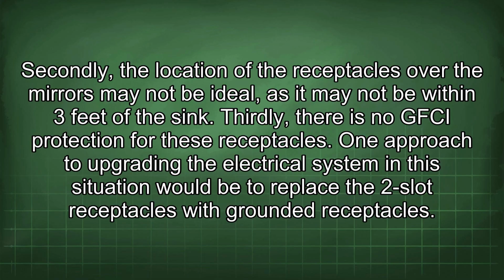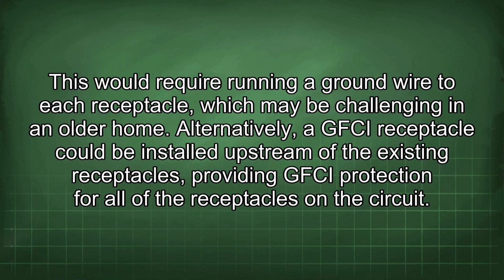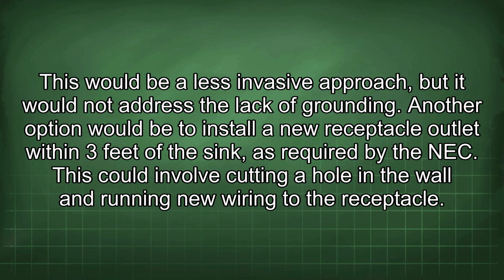One approach to upgrading the electrical system in this situation would be to replace the 2 slot receptacles with grounded receptacles. This would require running a ground wire to each receptacle, which may be challenging in an older home. Alternatively, a GFCI receptacle could be installed upstream of the existing receptacles, providing GFCI protection for all of the receptacles in the circuit. This would be a less invasive approach, but it would not address the lack of grounding.